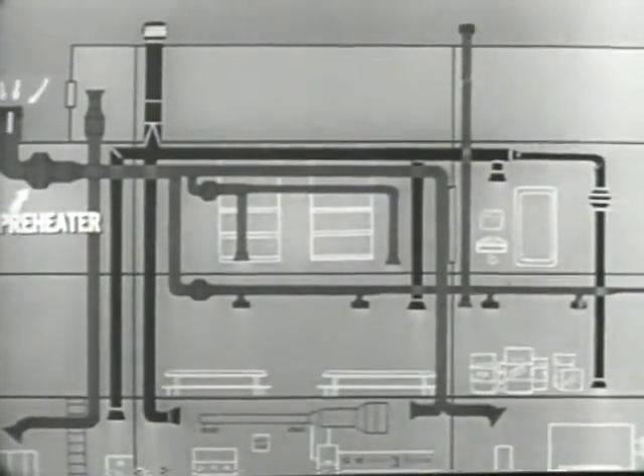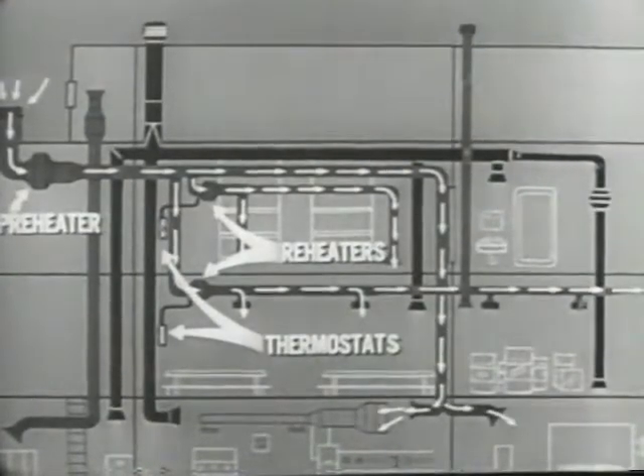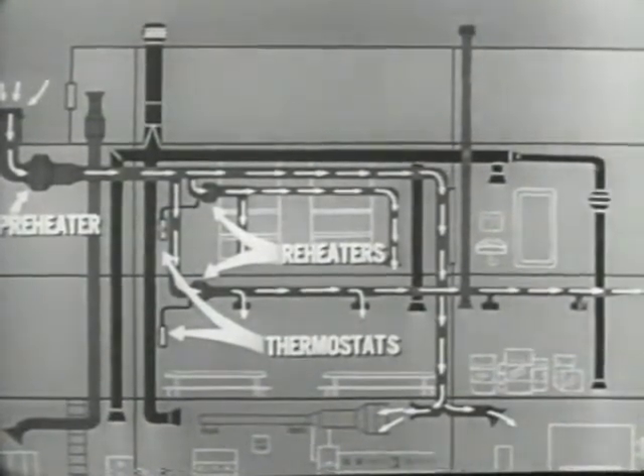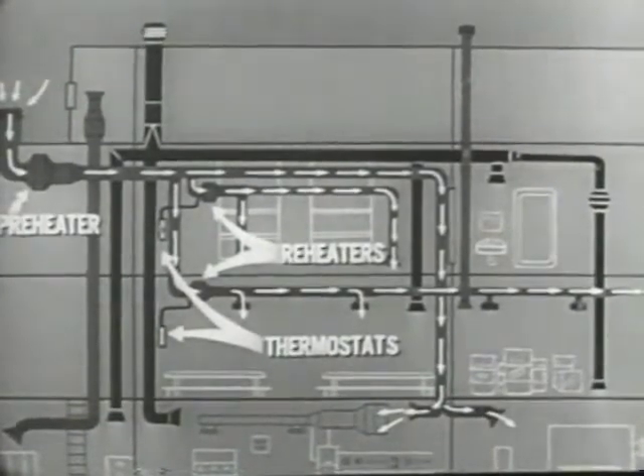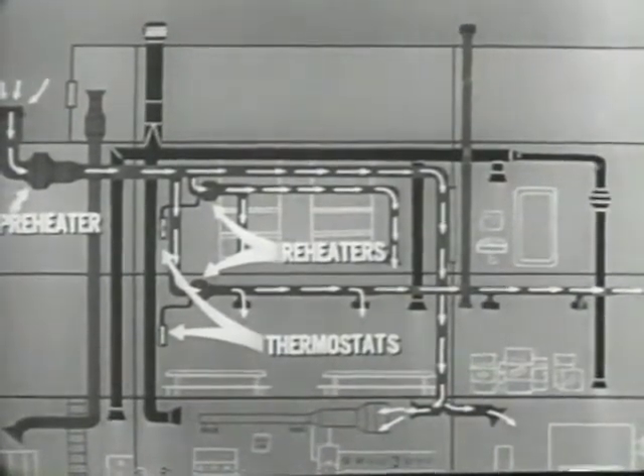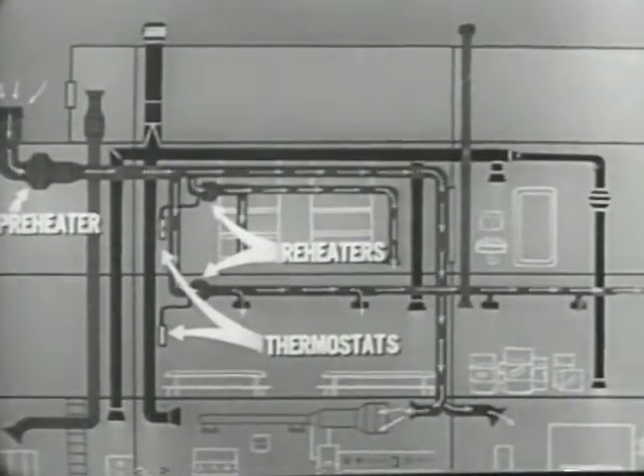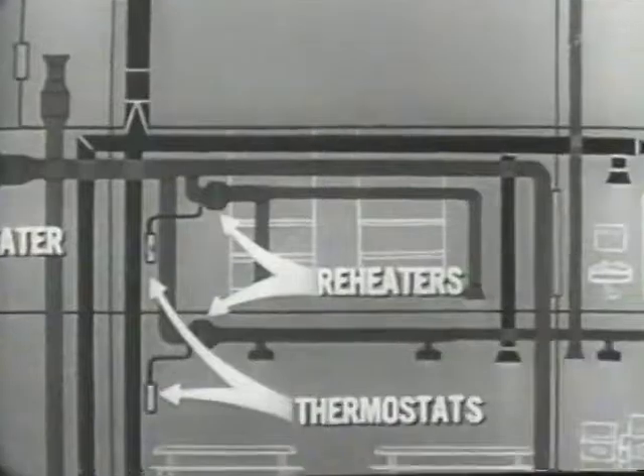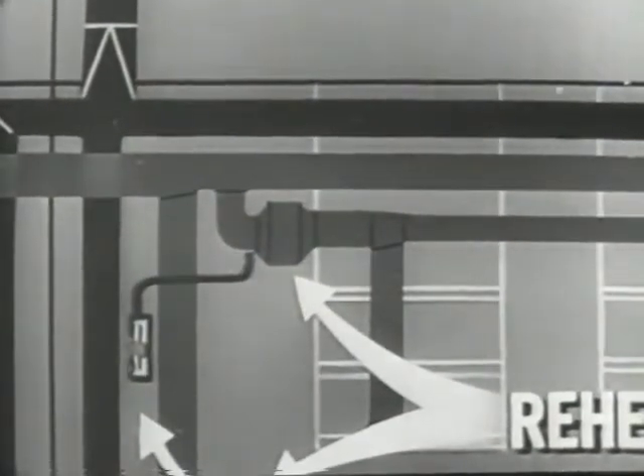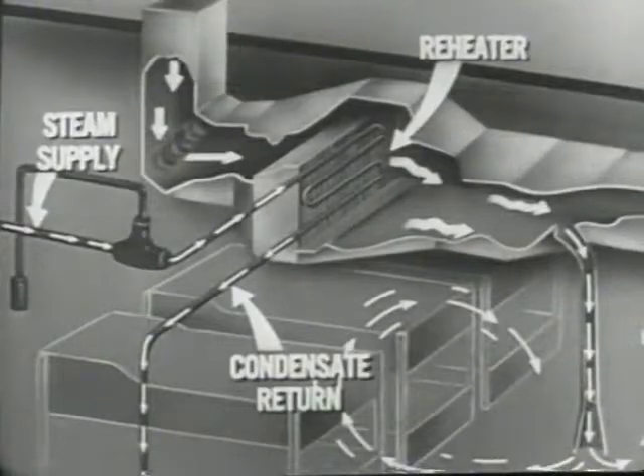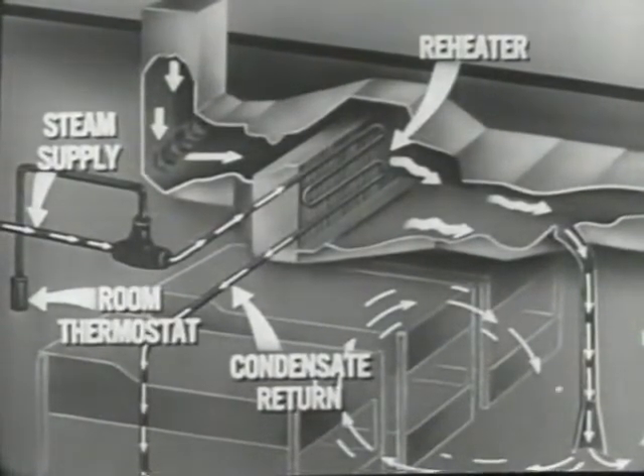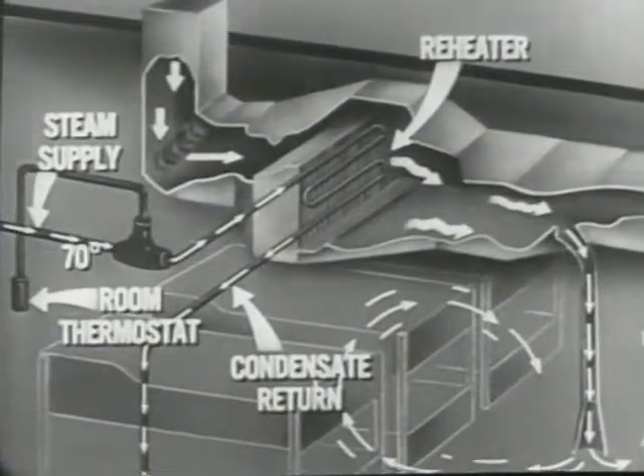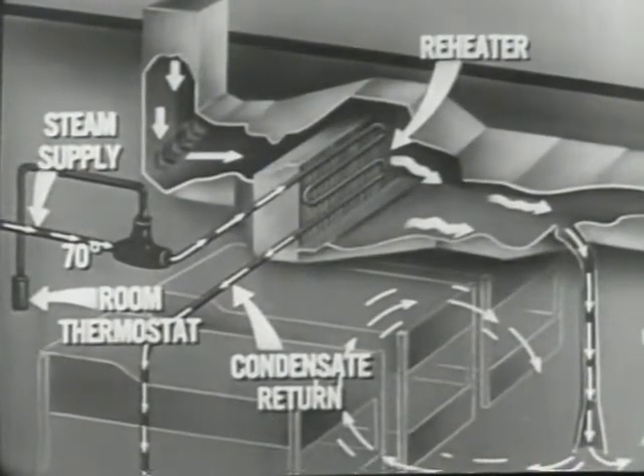Since living, berthing, and working areas may require a higher temperature, preheated air is passed through a reheater, similar in design to a preheater. One reheater sometimes serves a number of spaces called a zone, within which heat load requirements and weather exposures are similar. A room-type thermostat operates a valve which controls the steam flow through the reheater. Medical studies show that the thermostat in living compartments should be set at no more than 70 degrees Fahrenheit, and preferably between 65 to 68.